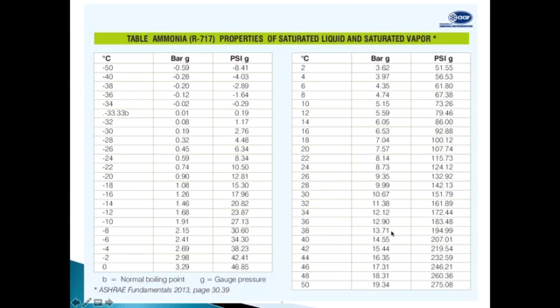If you are putting up a plant in very close vicinity to cities, it is better to go with low charge ammonia systems. But if your refrigerant plants are in an industrial zone, you find out whether your charge is exceeding the limit. Then you can consider what you want to go for.